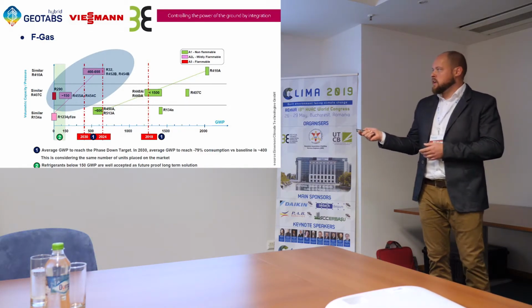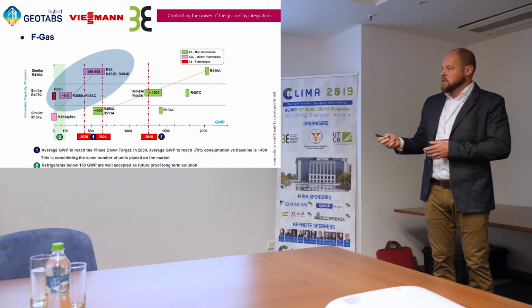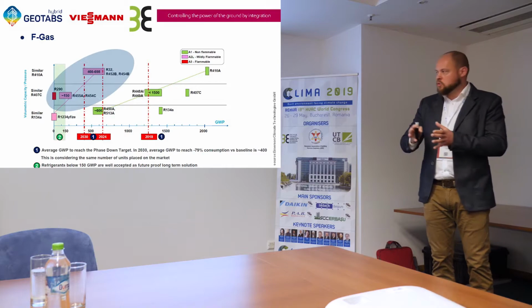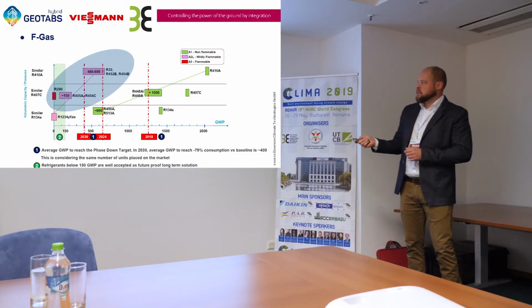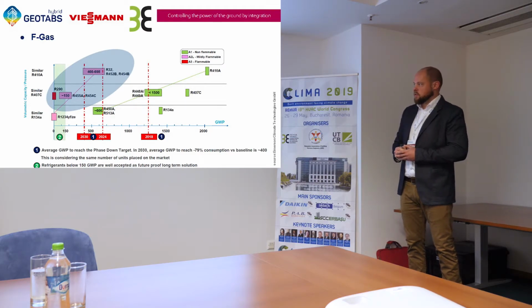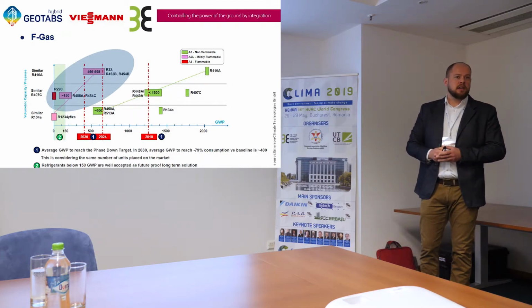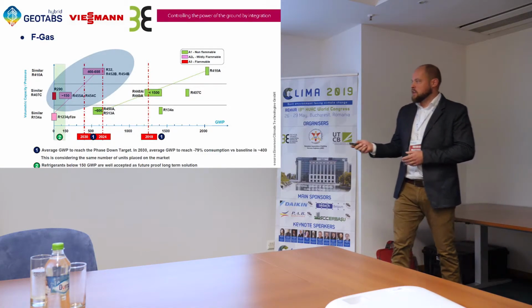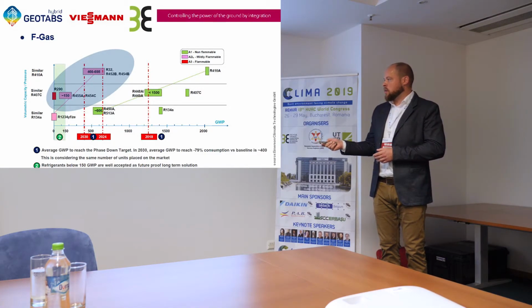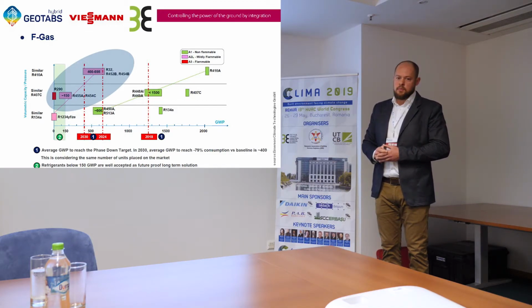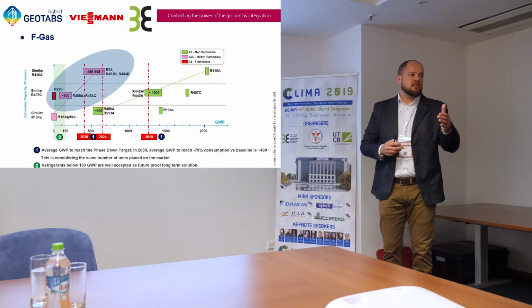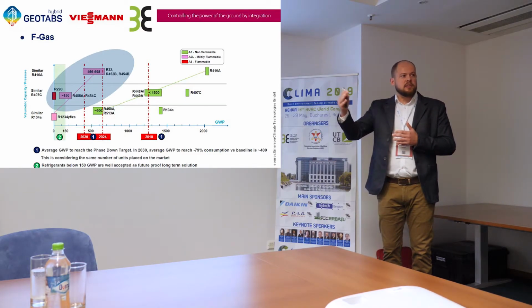The refrigerants that are here in this sector are just a temporary solution. When we go to the set point of 2030, they will not be able to use these refrigerants. So we have to go to even better refrigerants, such as the natural refrigerants, or R290, which is propane. That's a refrigerant that can be used. It has a very low GWP, and another refrigerant that is upcoming is a 1234ZE or YF. We are using this refrigerant in a special heat pump designed by Viessmann, and with that heat pump you can work with source temperatures up to 50 degrees, and you can make secondary temperatures up to 90 degrees.